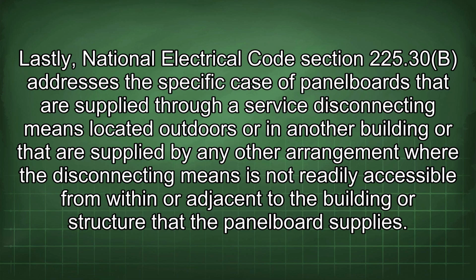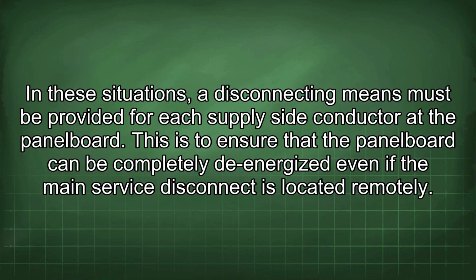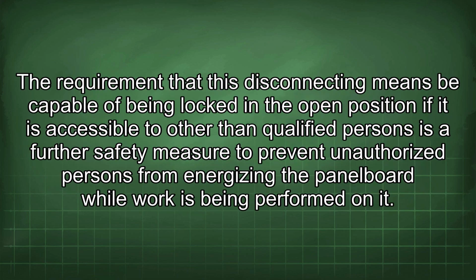Lastly, National Electrical Code Section 225.30(B) addresses the specific case of panel boards that are supplied through a service disconnecting means located outdoors or in another building or that are supplied by any other arrangement where the disconnecting means is not readily accessible from within or adjacent to the building or structure that the panel board supplies. In these situations, a disconnecting means must be provided for each supply-side conductor at the panel board. This is to ensure that the panel board can be completely de-energized even if the main service disconnect is located remotely. The requirement that this disconnecting means be capable of being locked in the open position if it is accessible to other than qualified persons is a further safety measure to prevent unauthorized persons from energizing the panel board while work is being performed on it.